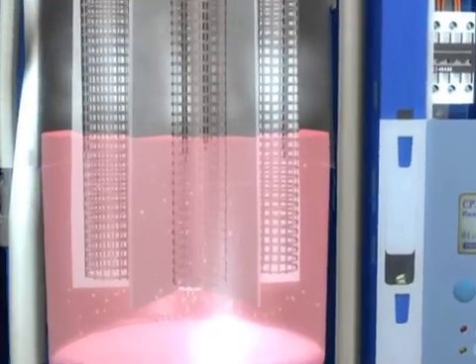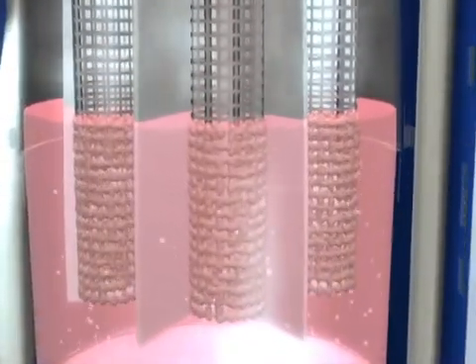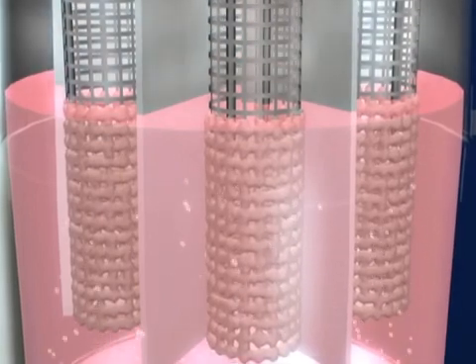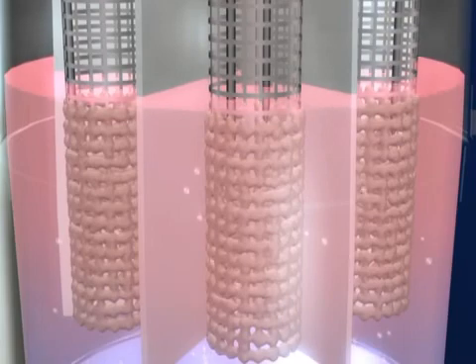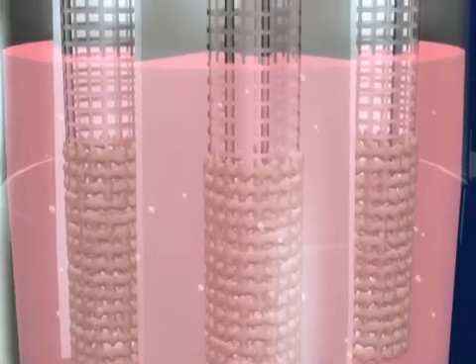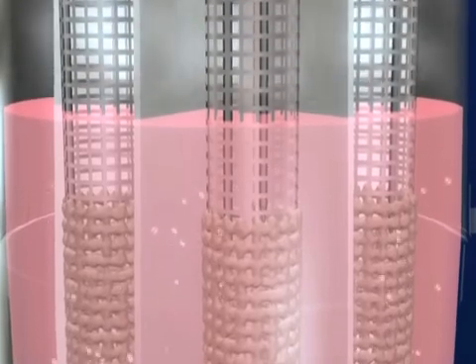Continuous operation builds up mineral deposits, even on the electrodes. Such incrustation decreases conductivity. The controller automatically recognizes this buildup of scale and reacts by increasing the water level to cover unused electrode surfaces. Therefore, the required steam production is not interrupted.